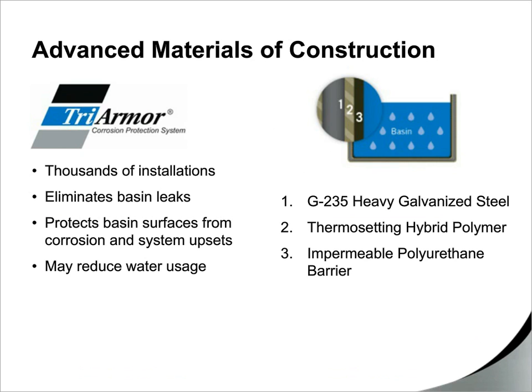Over the last several years, more advanced and cost-effective materials have been developed that offer an alternative to stainless steel. For example, a polyurethane coating on the cold water basin can offer a huge jump in corrosion protection over galvanized steel with a powder coating. This polyurethane coating, BAC offers it as the Tri-Armor corrosion protection system.